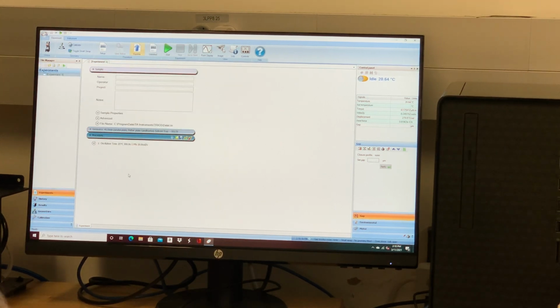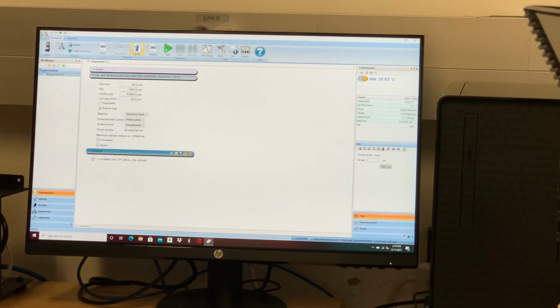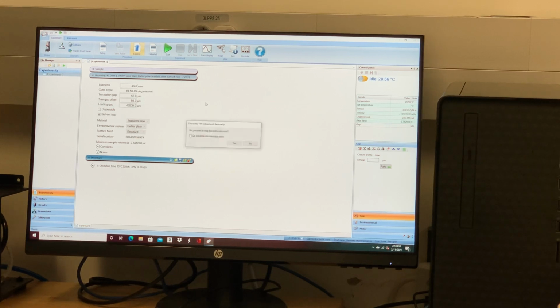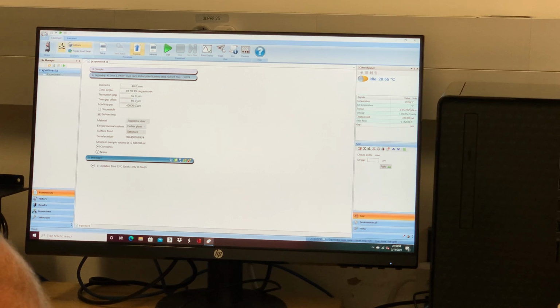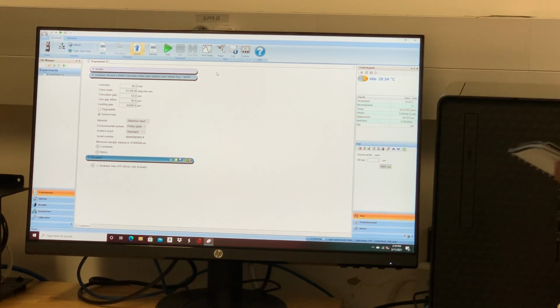And if we go to experiments here on the file manager side, and we go under experiment and geometry, right now we have the smart swap for the geometry toggled. Okay, so it will read this barcode. All the geometries have barcodes on them. If we install this and give it a second, it should read it and it should change this geometry to the 40 millimeter 2-degree cone. And there it is. So it read the geometry and it changed it to the 40 millimeter 2-degree cone.